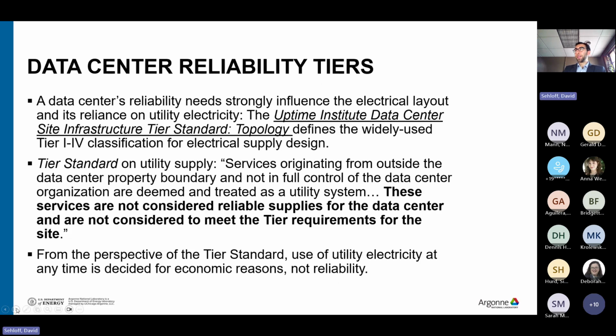There are different reliability tiers that apply for each of these. In the interest of time I'll skip through some of this, but the Uptime Institute tier standard for topology is a great reference. It's not too long, but it talks through the tier 1, 2, 3, and 4 classification for how redundant and reliable the electrical supply system is. Note that the tier standard is really based on on-site infrastructure and doesn't consider utility supply to be a reliable source, so meeting these tier reliability standards is really driven by on-site generation and distribution topology.